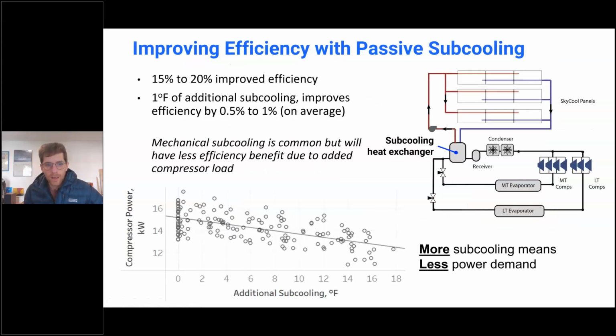So subcooling is one way to save energy in a refrigeration system or cooling system, and it essentially involves cooling refrigerant after it leaves the condenser. So typically the refrigerant leaves a condenser as a saturated liquid, and essentially subcooling is cooling that liquid as much as we can. It adds capacity to the liquid when it gets expanded in cases inside the system or after the expansion valve in the evaporators. And it's a way to essentially add between 15 to 20% efficiency to a cycle, and it's really going to be dependent on how much cooling you can provide.